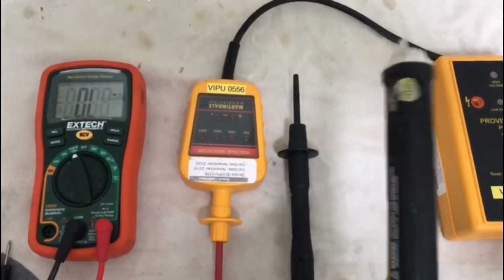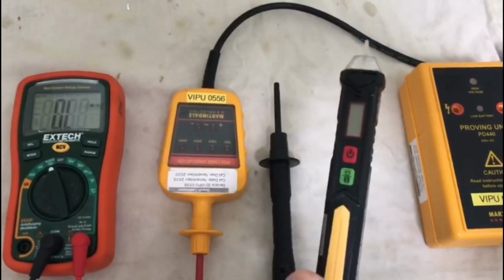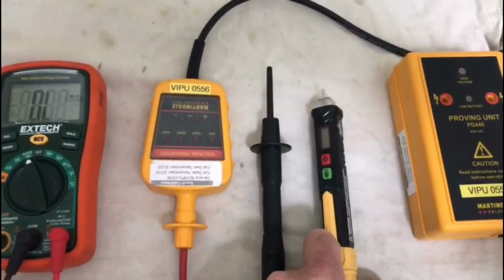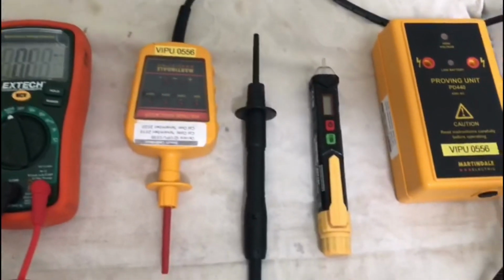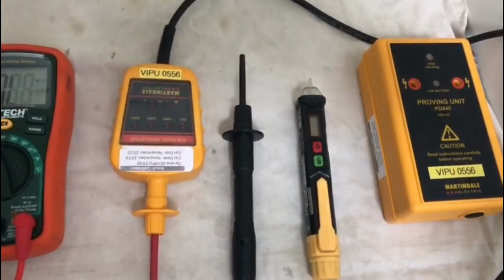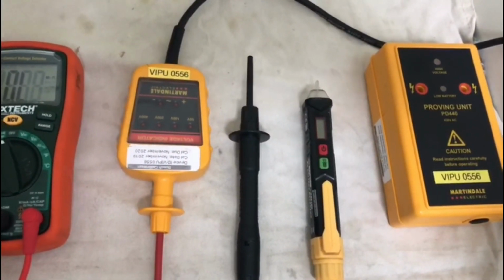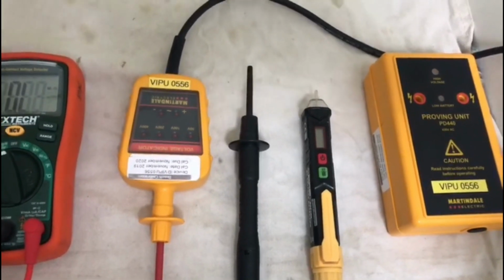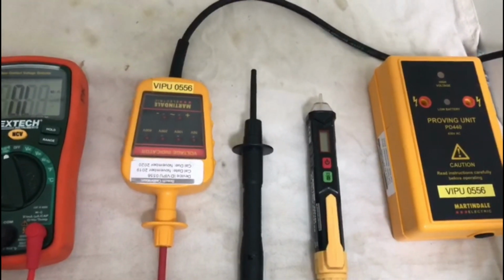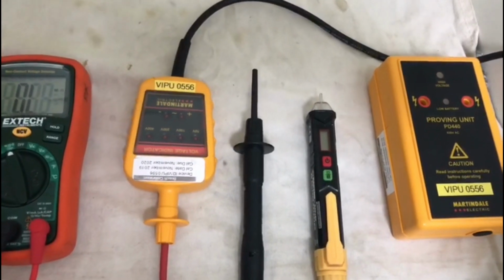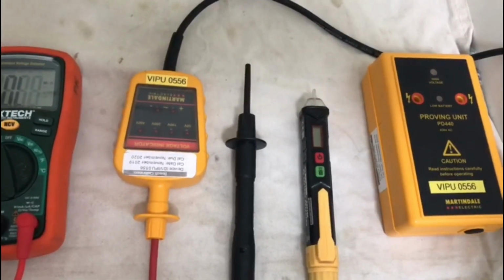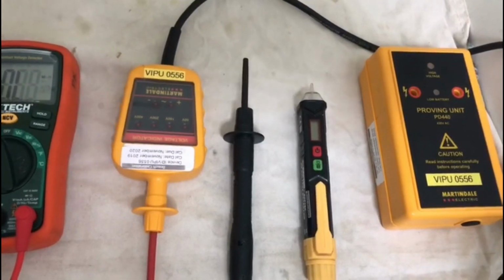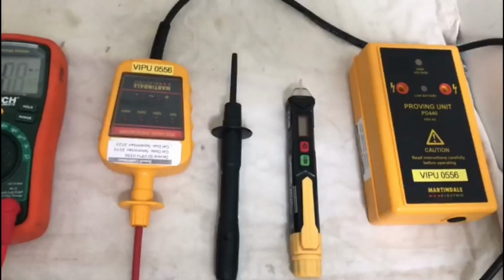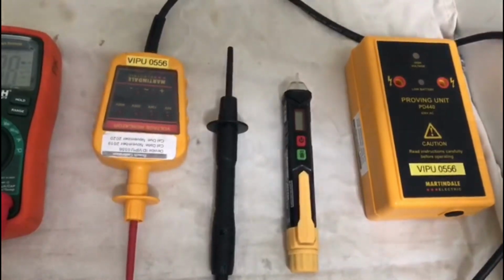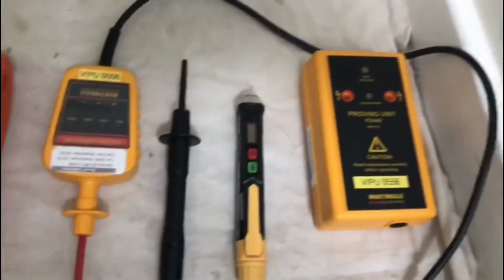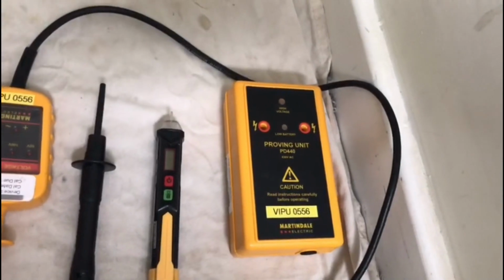Next is a non-contact voltage detector. That will tell you, without even touching the boiler, if it's live or not, or any live components. As the old saying goes, you prove that the unit's working, you use the unit, then you prove again, so that you know the equipment you're using is actually working. Not much point putting it on a test and then finding that it doesn't work, because you could be putting your hands into something live. So always work safely.